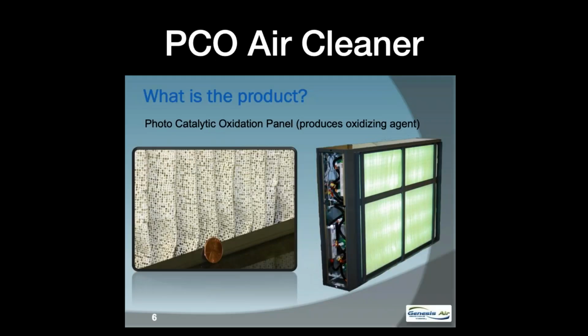I mentioned PCO air cleaner. I'm not sure how many people are familiar with PCO. PCO stands for photocatalytic oxidation. This module is 6 inches in depth, and between the 6-row cooling coil and the two-row hot gas reheat coils, there is a 6-inch slide-in filter tray in which these PCO air cleaners can be installed. This is not a Cultiva Systems product, but it's available and can be factory installed.